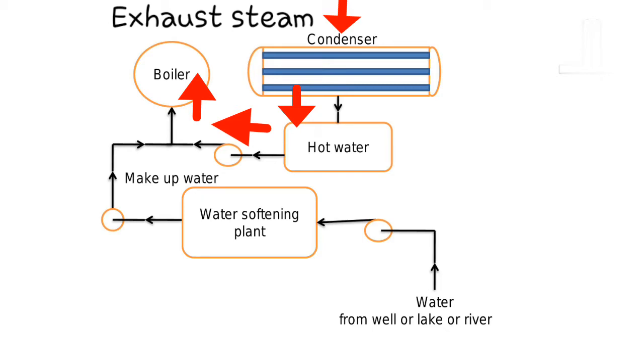In this process, some water is lost throughout the cycle for blowdown and leaks. The loss varies from 1 to 3 percent during normal operation and 5 percent during startup period.